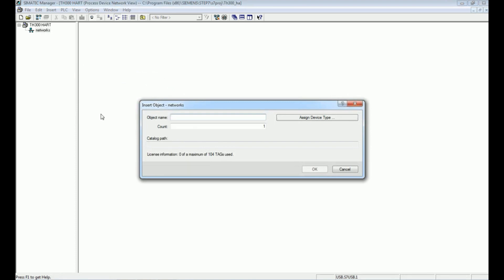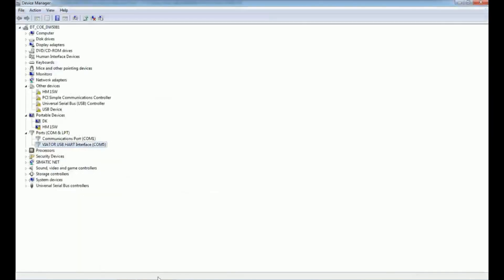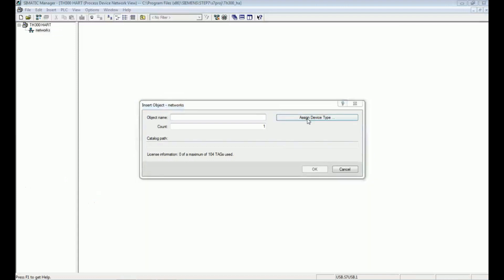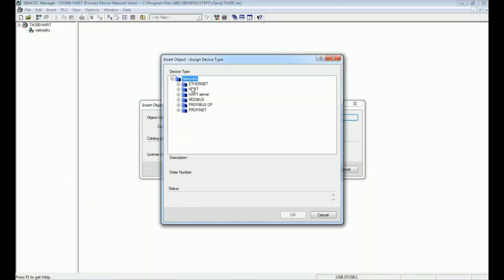Before we add this network, we must know the communication port connected to the PC. From the Device Manager we open the ports, and we will see the COM port number that the HART modem is connected to. This COM port number must match our communication network setting. I will now go to the Assign Device tab and select the HART modem network.